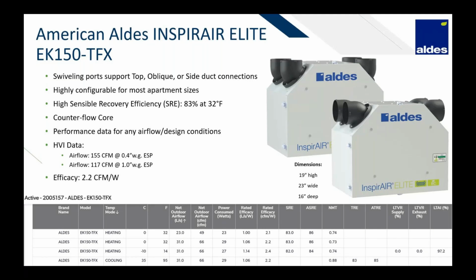You have a high sensible recovery efficiency of 83% at 32 degrees, and that's at 66 CFM. And you can even get, it's funny because right now you couldn't really extrapolate that out, but we do have the core simulation data to once again help you develop a schedule outside of that. It also has very good airflow, so 155 CFM at 0.4 inches static pressure and 117 CFM at 1 inch, and again, good efficacy of 2.2 CFM per watt.